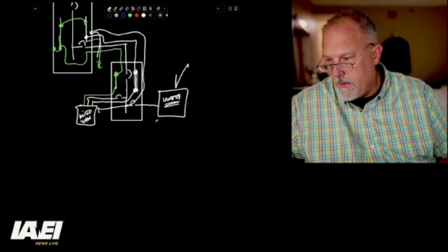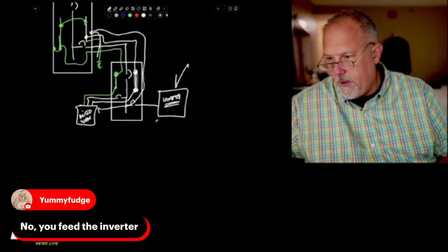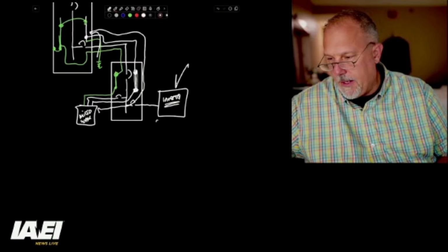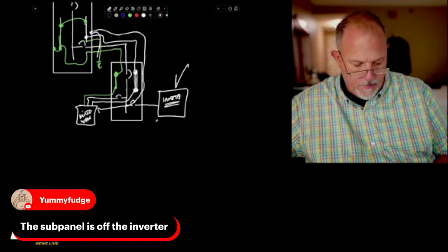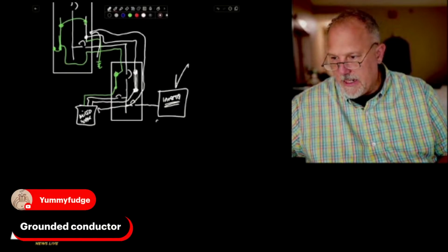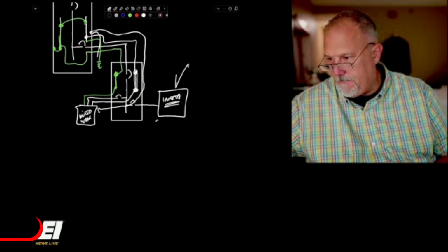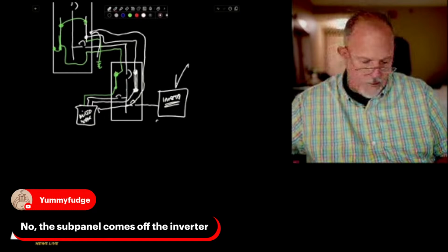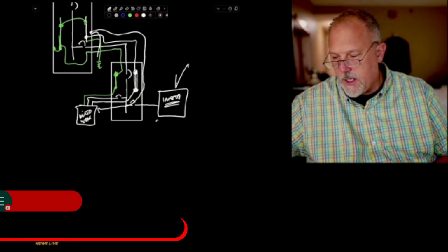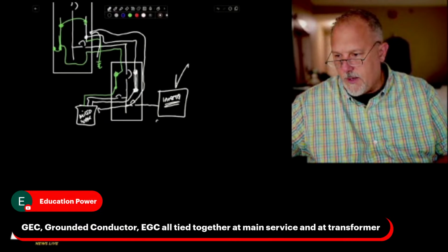No, you feed the inverter. Yeah, but it's all connected. The sub panel is off the inverter. Yep, I think I drew that. Grounded conductor. Got that. The sub panel comes off the inverter. So, oh, what's Robert say? GEC, grounding electrode conductor. Yep.